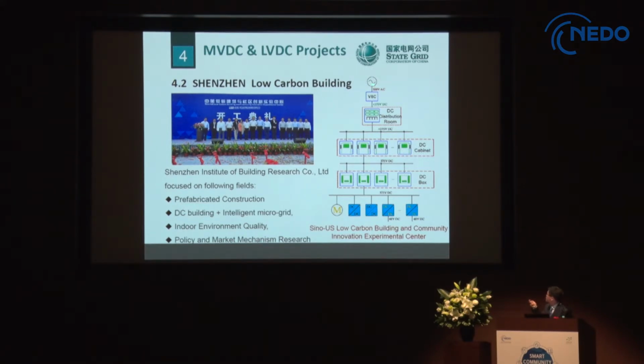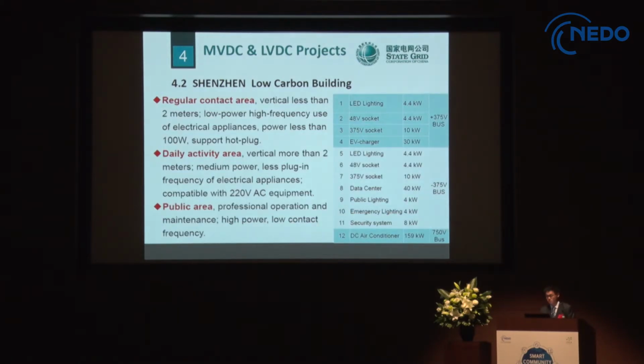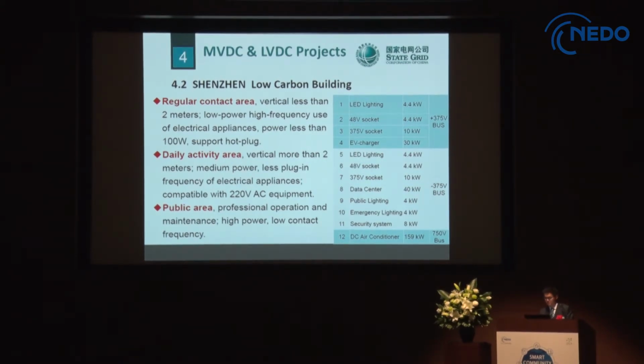This building is supplied by 380 volt AC, and it is rectified into 375 volt DC, and distributed to other DC equipment. Here is a table listing the DC equipment. It contains LED lighting, 48 volt sockets, 375 volt sockets, and EV chargers. The total power of the positive 375 volt bus achieved about 50 kilowatts, and the negative bus achieved 80 kilowatts, and the DC air conditioner is connected to the 750 volt bus.